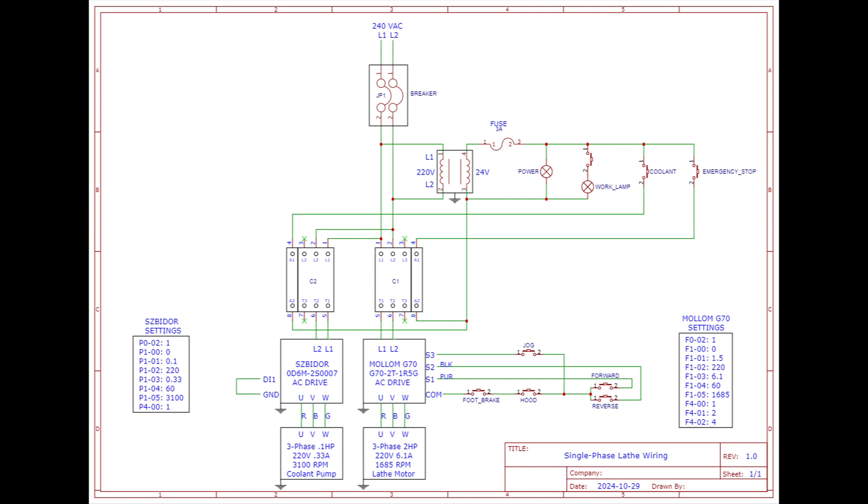The emergency stop switch powers terminal A1 of contactor C1, which in turn energizes the contactor. It turns on the Mollom G70 AC drive or VFD. The output of that feeds the three-phase lathe motor for the gearbox.